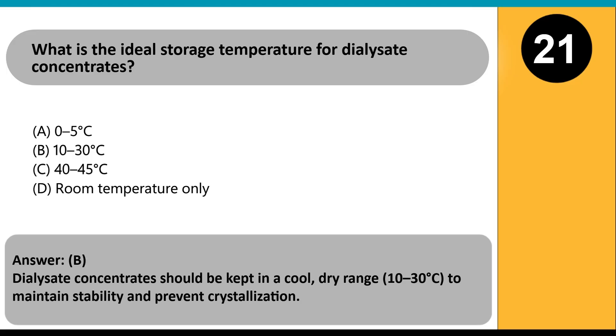Which safety check ensures prevention of air embolism? A. Air detector alarm and chamber inspection. B. High dialysate pressure. C. Heparin lock. D. Venous sampling. Answer A. The air detector ensures no air enters the venous return; visual and mechanical checks are mandatory. What is the ideal storage temperature for dialysate concentrates? A. 0 to 5 degrees Celsius. B. 10 to 30 degrees Celsius. C. 40 to 45 degrees Celsius. D. Room temperature only. Answer B. Dialysate concentrates should be kept in a cool, dry range of 10 to 30 degrees Celsius to maintain stability and prevent crystallization.